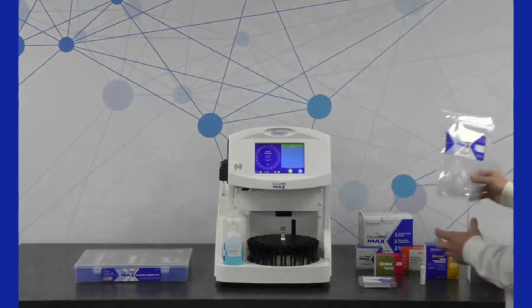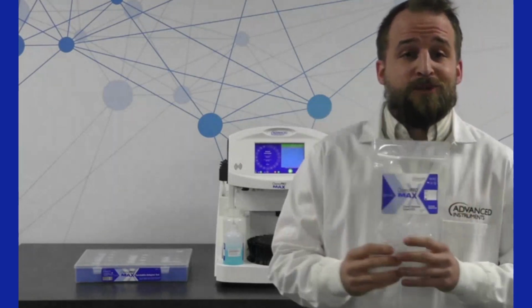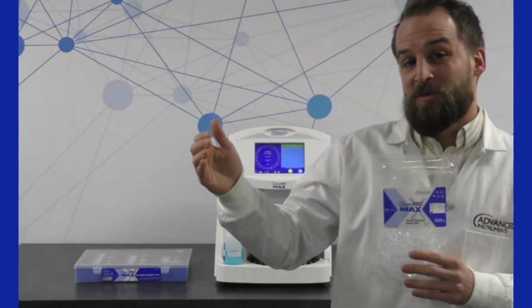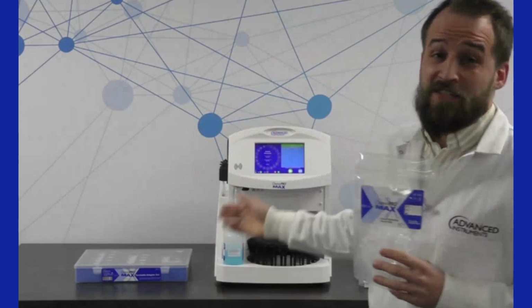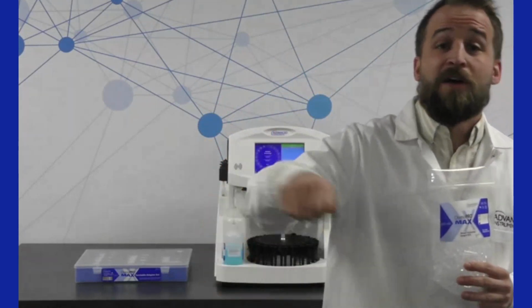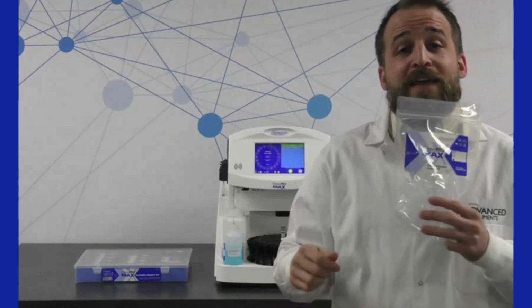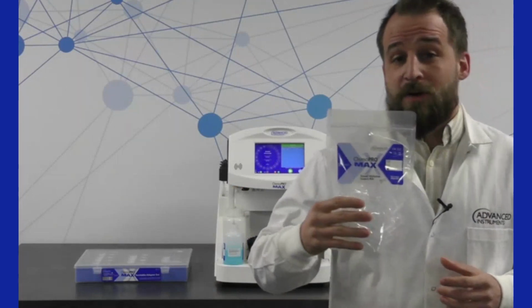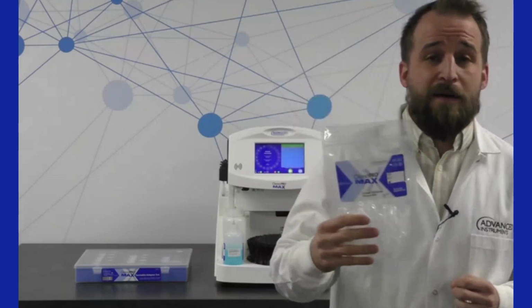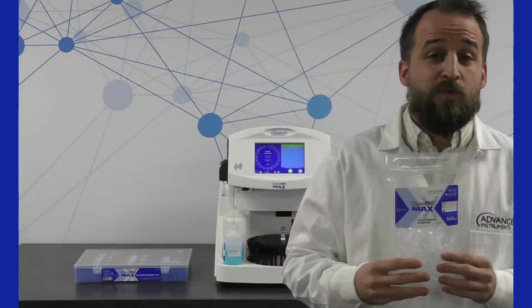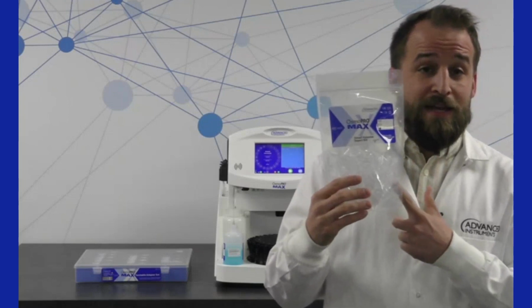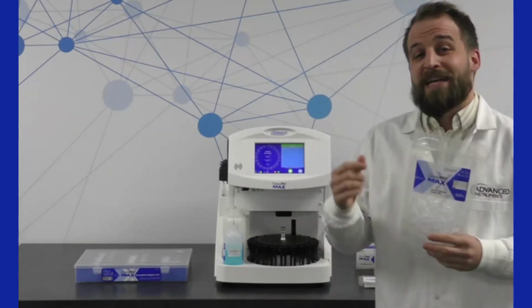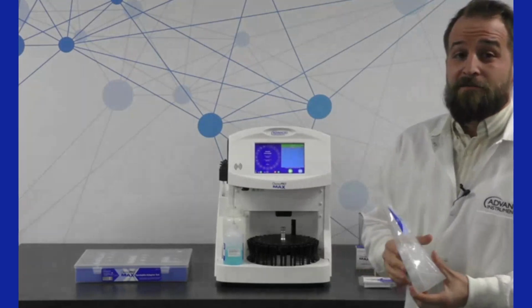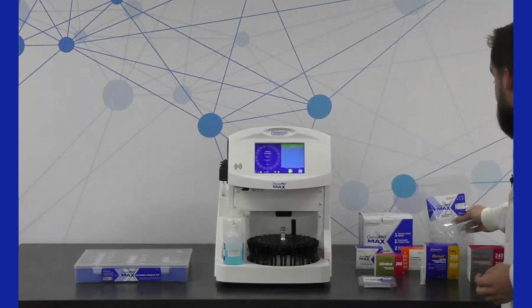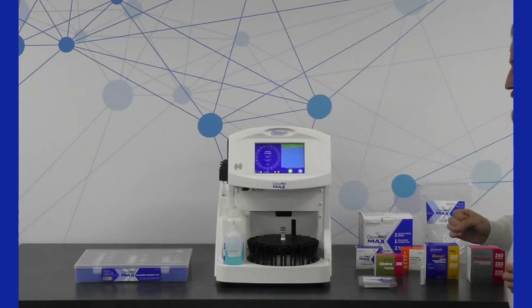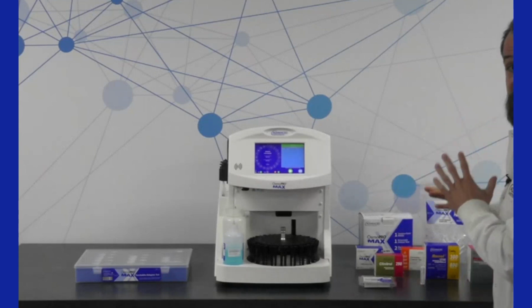And then, as promised, I had mentioned what happens if you have a short sample. So just to communicate that, the primary sample tube uses 480 microliters. That's actually what the instrument is going to take from your urine or serum tube or whatever other primary tubes you're putting on the instrument. If you have a short sample, or a sample that was a tough stick or a pediatric sample, and you need to run a smaller volume, you can use an insert. And the instrument will aspirate just 190 microliters instead of that full 480 to perform the testing off of the small volume insert kit. Okay, so that's all of the consumables that you get.